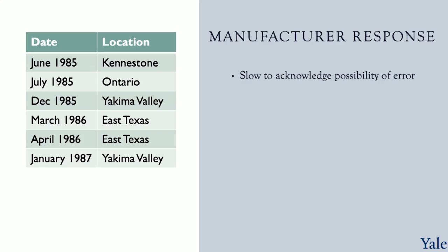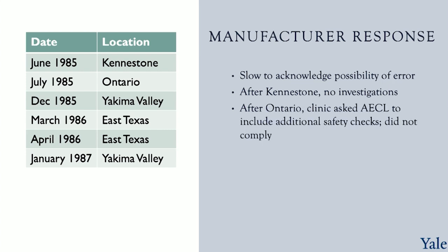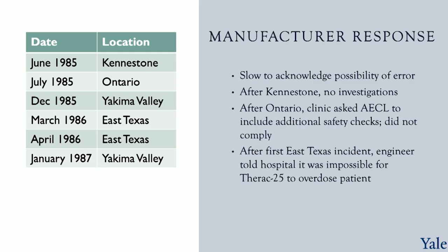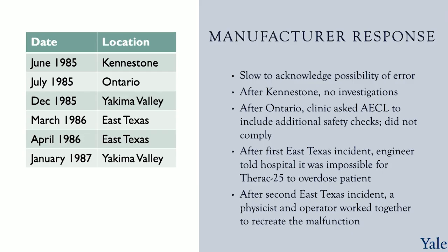It took far too many incidents for the manufacturers to even acknowledge the possibility of error. After the first incident, no action was taken to investigate the safety or to warn other physicians using Therac-25. After the second incident, the clinic asked AECL to include additional safety checks, but AECL did not comply. After the first Texas incident, an engineer told the hospital that it was, quote, impossible for Therac-25 to overdose the patient. The second East Texas incident involved the exact same operator, who again used the edit up key to quickly change the mode from x-ray to electron.